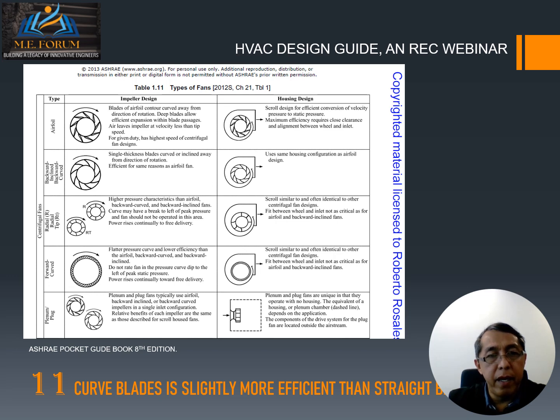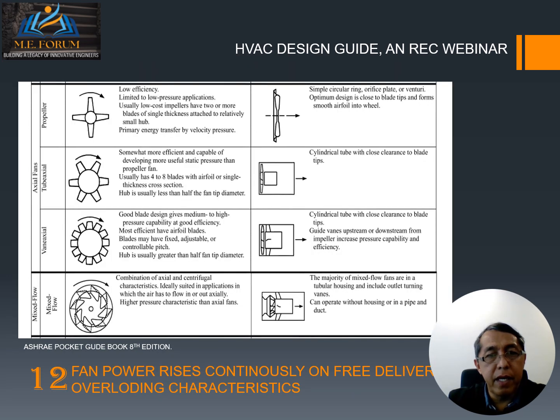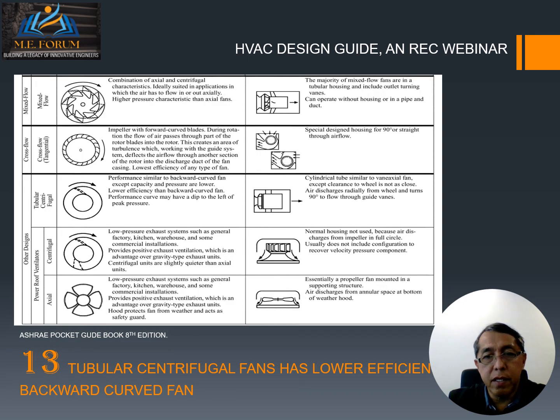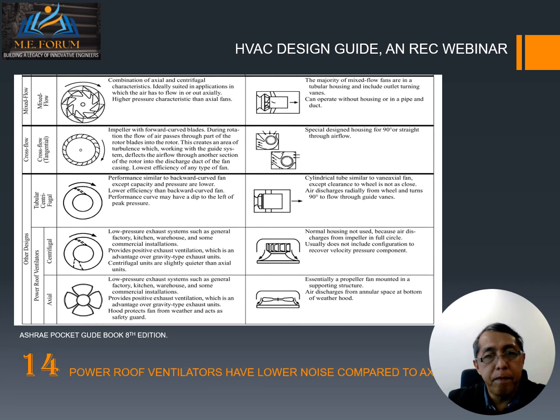Number 11, curved blades are slightly more efficient than straight blades. Fan power rises continuously on free delivery and overloading characteristics. Number 13, tubular centrifugal fan has lower efficiency than backward curve fan.